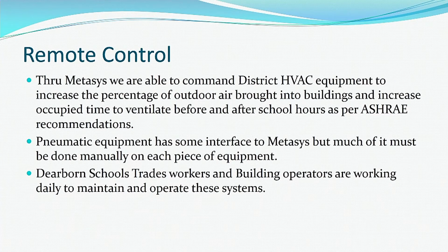With remote control through Metasys, we are able to command district HVAC equipment to increase the percentage of outdoor air brought into the building and to increase the occupied time to ventilate before and after school hours, as per ASHRAE recommendations. So we've done that in the district. We've commanded all our outdoor air dampers to a minimum of 20% outdoor air to mix with that room air and increase the ventilation to all the spaces in the district. And we're increasing the occupied times so that there's ventilation before and after staff and whoever else comes in the building, to pre-purge and ventilate, in addition to ensure we get the air clean.